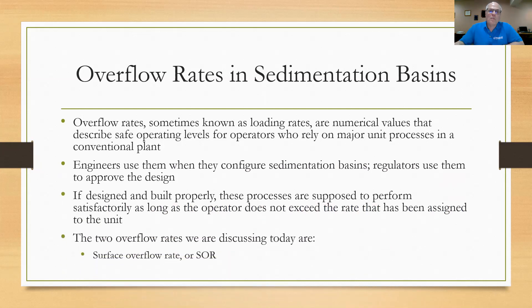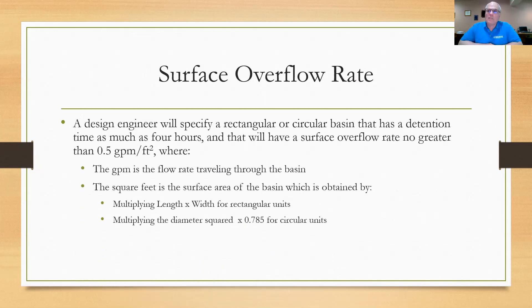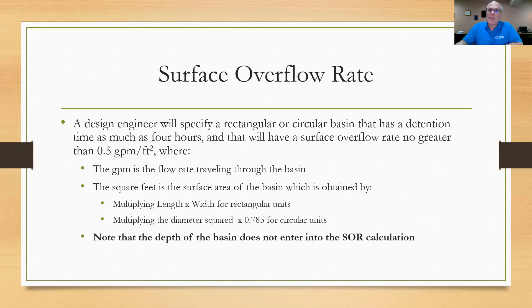The parts we're discussing today are surface overflow rate, which we write as SOR, and weir overflow rate, which we'll call WOR. A design engineer will specify a rectangular or circular basin with a detention time of up to four hours for sedimentation, with a surface overflow rate typically no greater than 0.5 gallons per minute per square foot. The square feet is the surface area obtained by multiplying length times width for a rectangular basin, or diameter squared times 0.785 for a circular basin. Note that the depth of the basin is not used in these calculations.